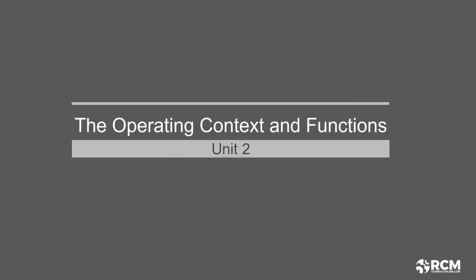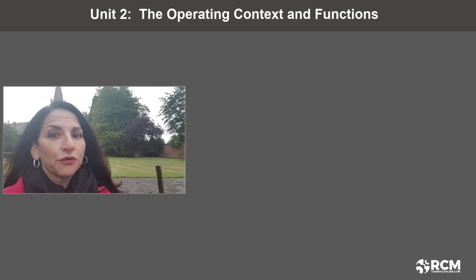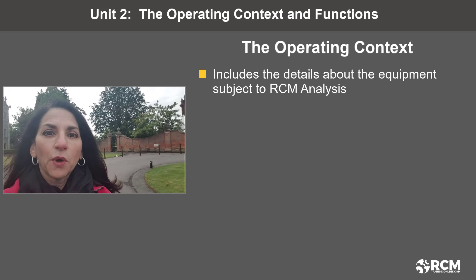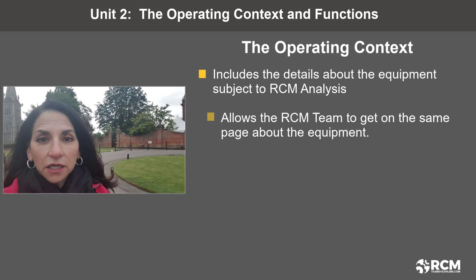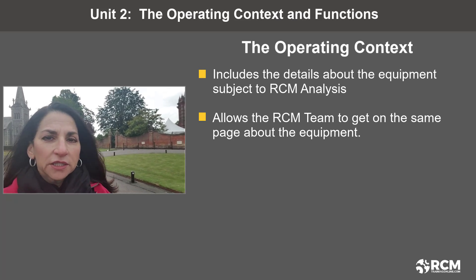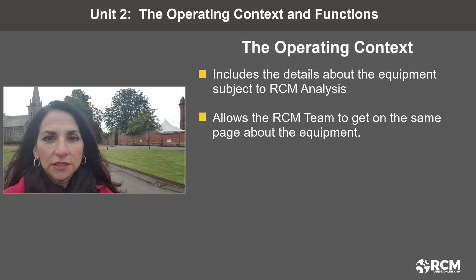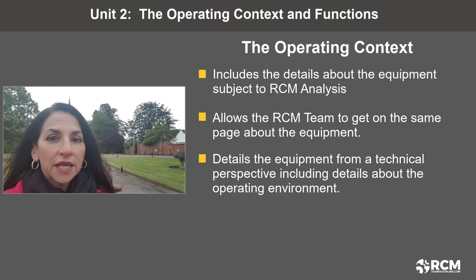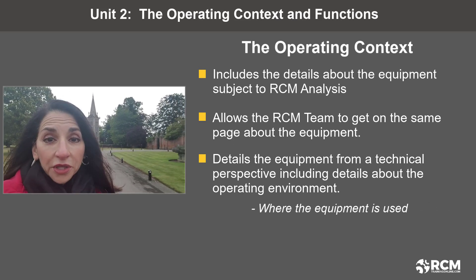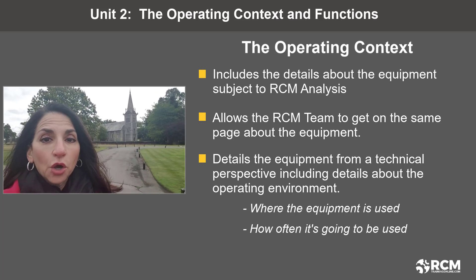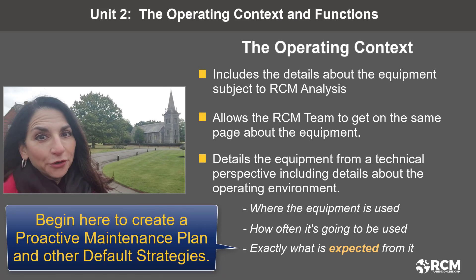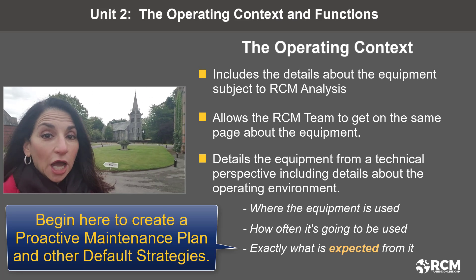The operating context and functions. When you do reliability centered maintenance the right way, you start by writing an operating context, which is basically like a story of what the equipment is all about. It allows the facilitator and the working group to get on the same page about the equipment. It details the equipment from a technical perspective but also identifies the operating environment — where the equipment is used, how often it's used, and exactly what is expected from it.